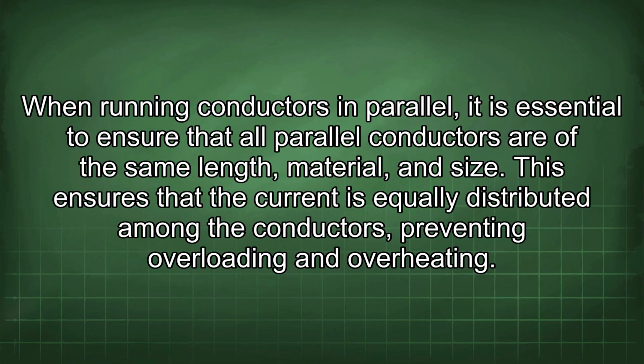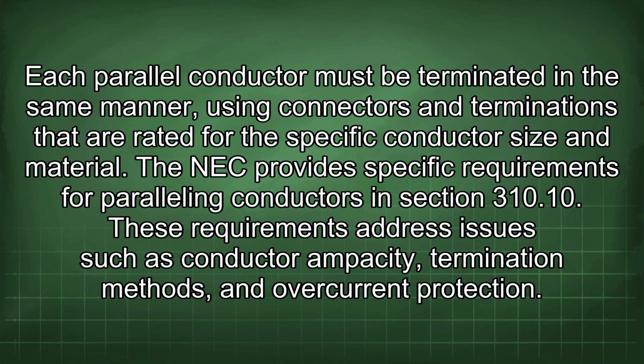When running conductors in parallel, it is essential to ensure that all parallel conductors are of the same length, material, and size. This ensures that the current is equally distributed among the conductors, preventing overloading and overheating. Each parallel conductor must be terminated in the same manner, using connectors and terminations that are rated for the specific conductor size and material. The NEC provides specific requirements for paralleling conductors in section 310.10. These requirements address issues such as conductor ampacity, termination methods, and overcurrent protection.